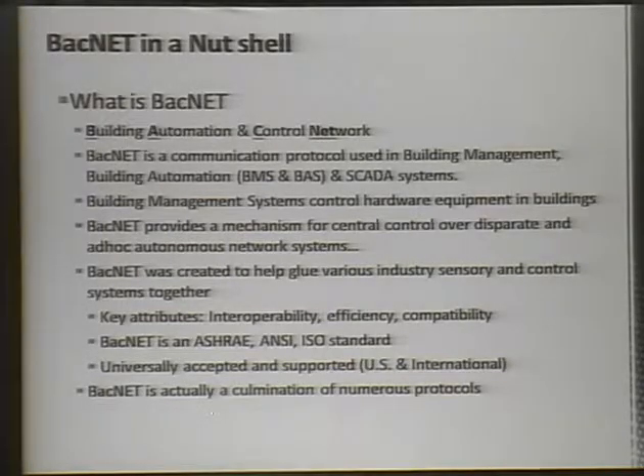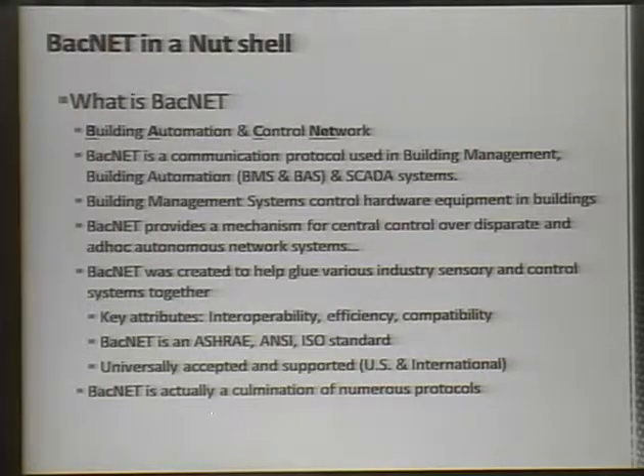What is BACnet? BACnet stands for Building Automation and Control Network. At its simplest, it's the communication protocol used by building management, building automation, and SCADA systems. Think of BACnet as the TCP/IP controlling all these different sensors. It sits below the SCADA system. I'm focusing on the gateway devices that control the endpoints. It was really designed to pull together disparate systems — Honeywell, Siemens, valves, HVAC, elevators — kind of analogous to TCP/IP. It doesn't care what's on the endpoint; as long as you're talking this common protocol, it lets you control, manipulate, and get data.